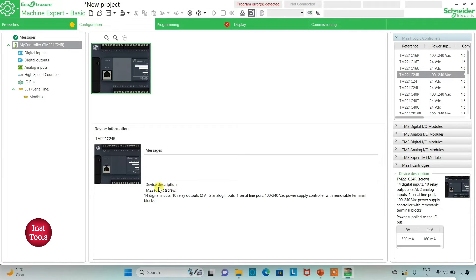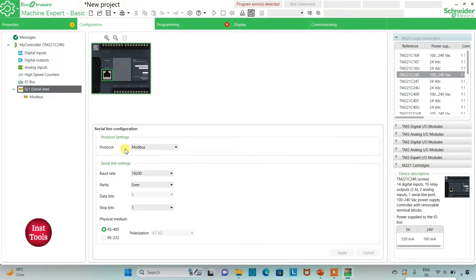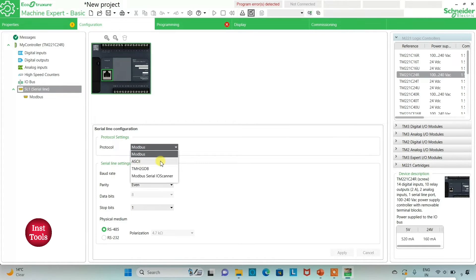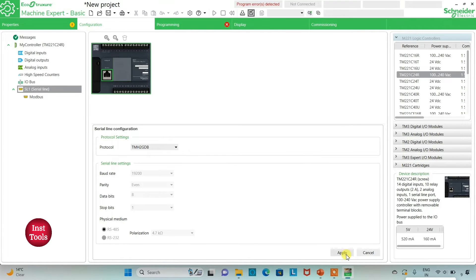The TM221C24R has 14 digital inputs, 10 relay outputs, 2 analog inputs, 1 serial line port, and a 100–240V AC power supply with removable terminal blocks. I can also go to the Serial Line settings and select protocol. I will keep it as TMH2GDB, which means there is no need to manually set the serial line settings, and then click Apply.